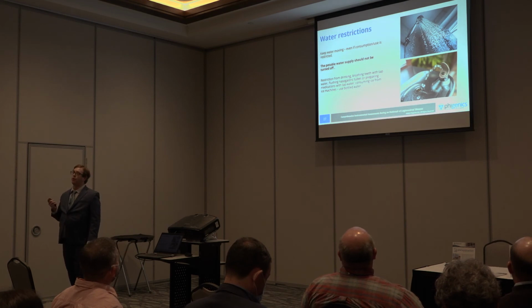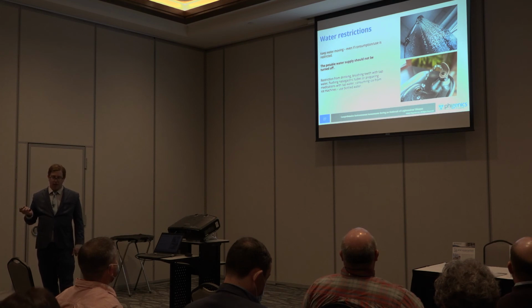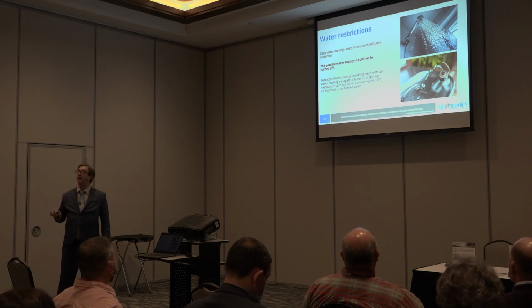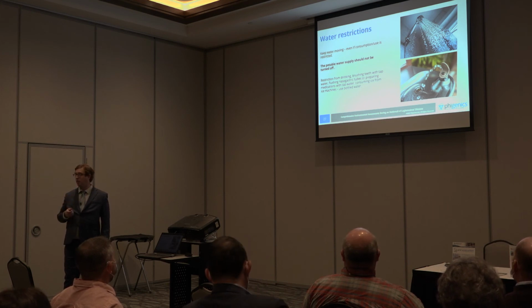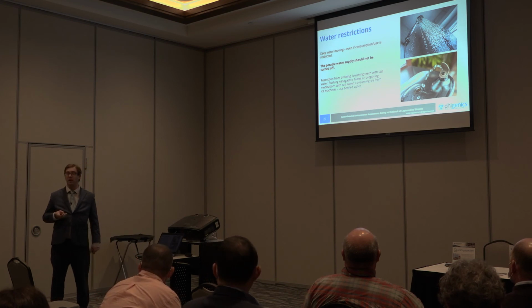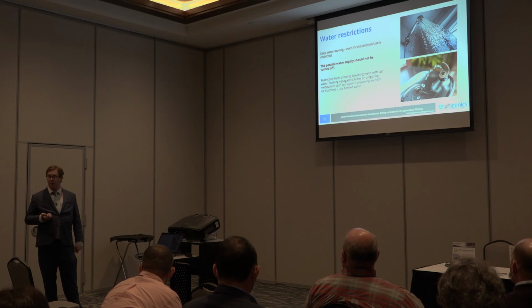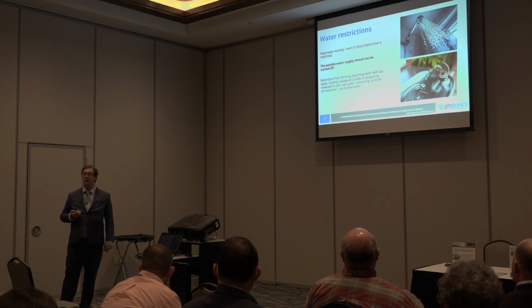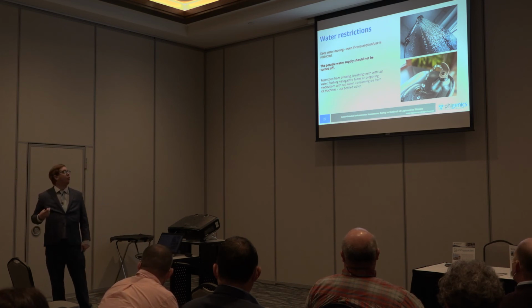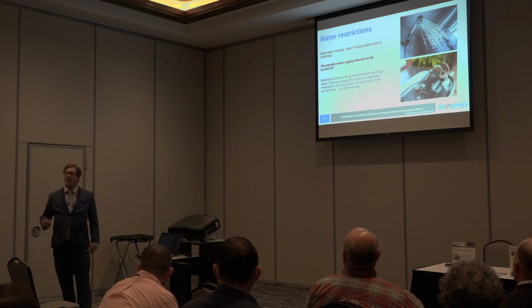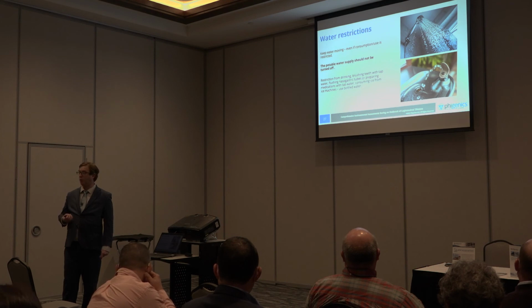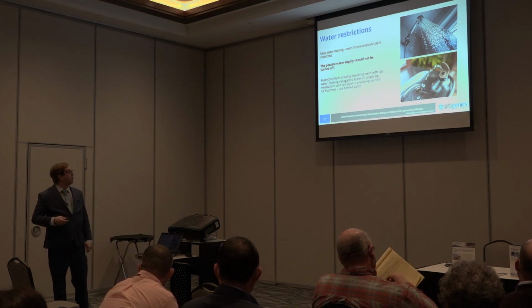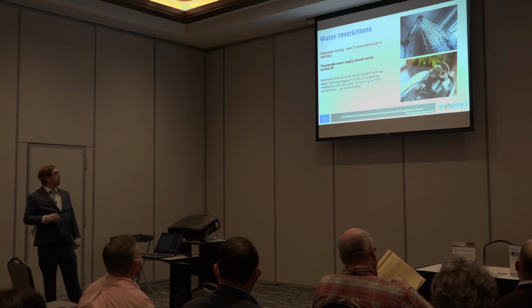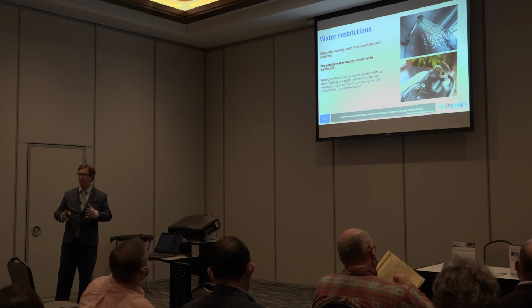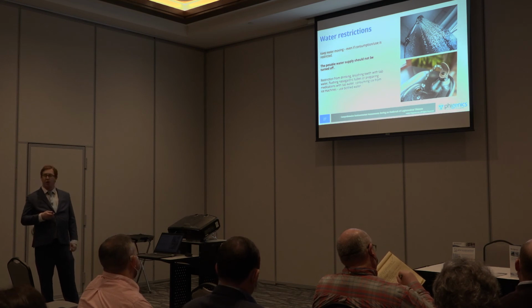Water restrictions. A lot of the time, going back to the idea of approaching water management from an emergency point of view, facilities will find Legionella in their water system, or there may be a potential case where someone was exposed to the water system at their facility. What shouldn't happen is turning off your water system entirely. Water restrictions are important, especially if someone could be exposed to things like showers and spas, but you want to keep water flowing. That's one of the main reasons why Legionella grows so well in a facility's building water system: there is that potential for stagnation and water age. So the potable water supply should not be turned off. You can restrict use of showers and other aerosol generating devices, but keep the regular routine maintenance going.